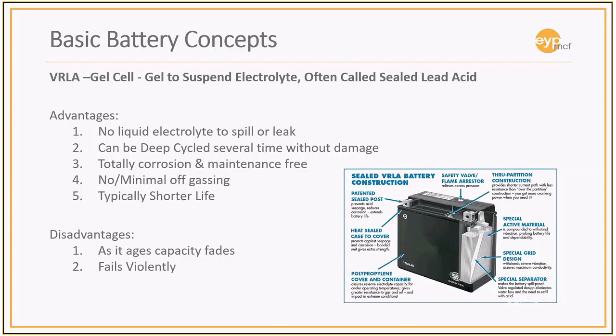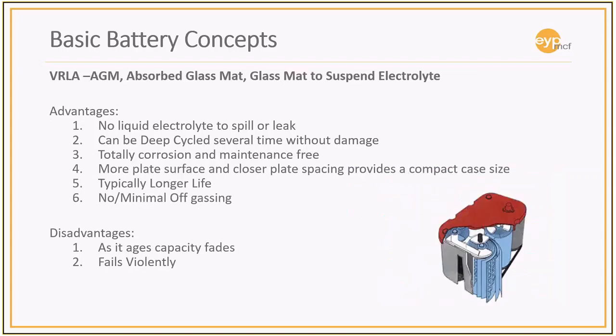But when these fail, they typically fail violently. When a flooded cell fails, it typically fails open, so you actually lose voltage. But in the case of a valve-regulated cell, especially these gel cells, they tend to fail violently. The absorbed glass mat is basically the same configuration. No liquid electrolyte. You can get a deep cycle cell. They typically last longer, so you'll find these are more in the 10-year time frame.